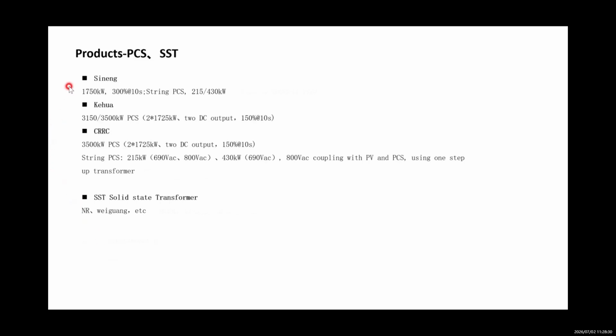The next product category is PCS and SST. For PCS, we introduced some mainstream PCS manufacturers: Sineng, Kehua, and CRRC. For Sineng, they have launched a new version of centralized PCS at 1750 kilowatt. This PCS has significant overload capability, 300% of rated power for 10 seconds, which is a requirement from the domestic market.